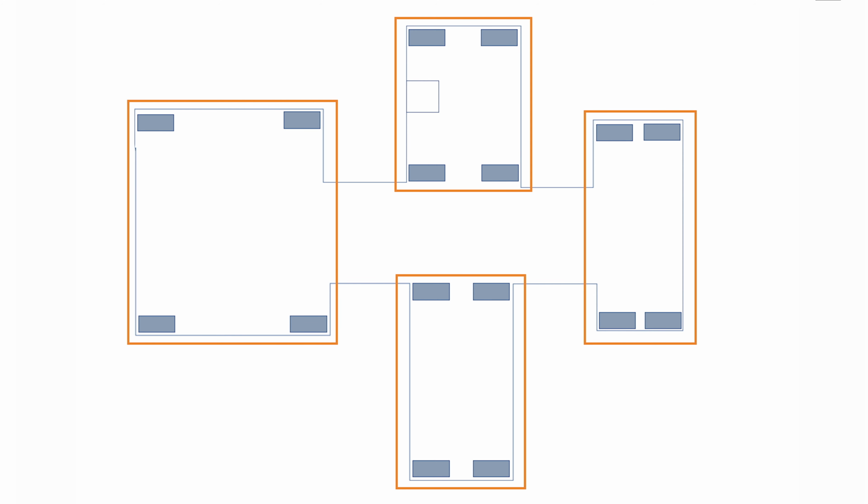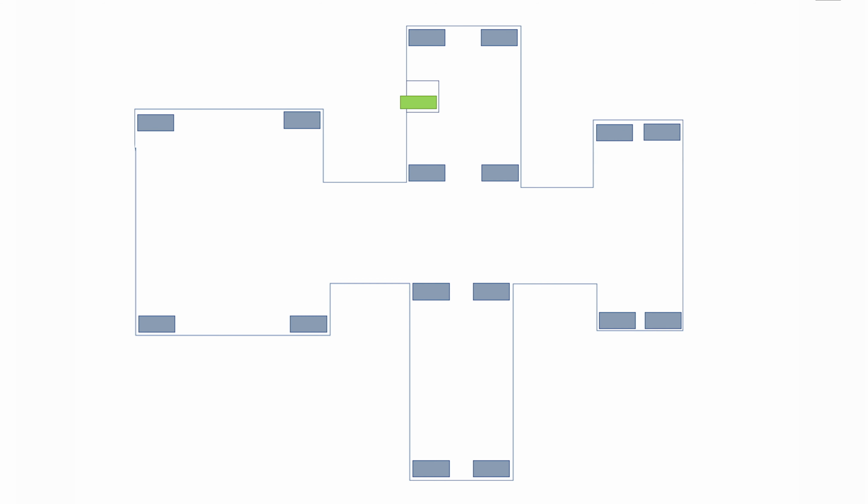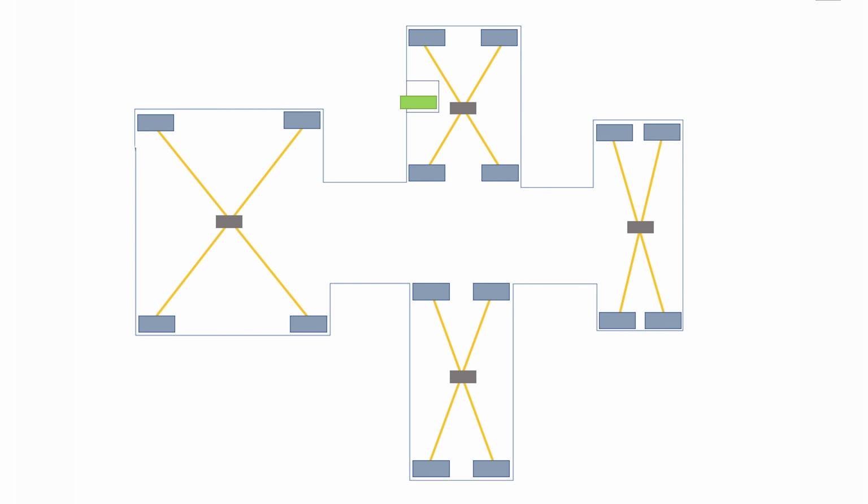Let's say we need 4 switches in 4 locations of each wing for a total of 16 switches. The ONSS8 aggregation switch is to be located in the control room here. Let's say that after looking at conduits, we decide to connect the 4 switches in each wing through a 1:4, then add a 5th 1:4 splitter to connect the 4 wings to the center. Finally, connect the center splitter back to the MDF or control room.